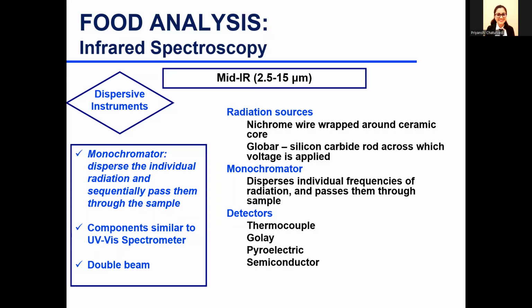So you can get some really affordable mid-IR. Usually what you're sacrificing is the precision of detection. Your wavenumber or wavelength windows might be plus or minus 5 instead of plus or minus 2 or 0.2. So you're sacrificing accuracy and precision because of the optics and the electronics.